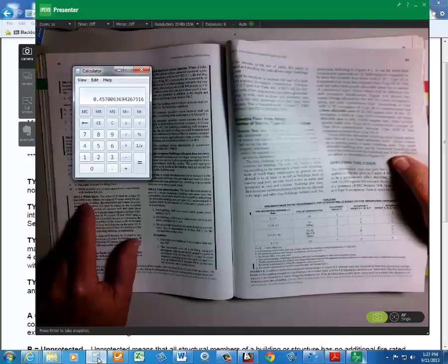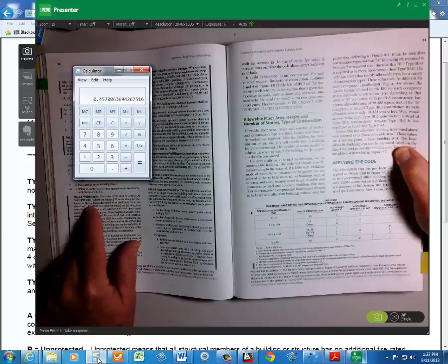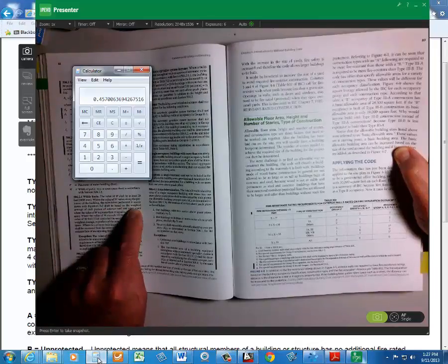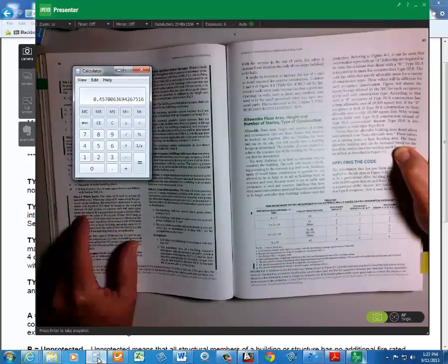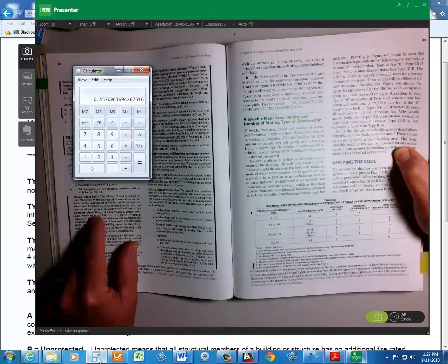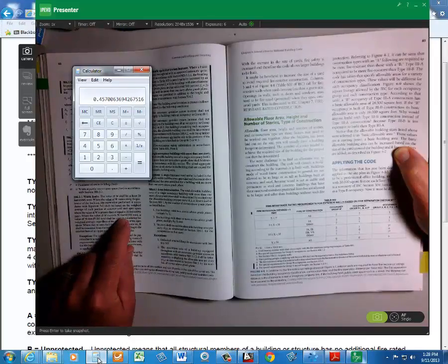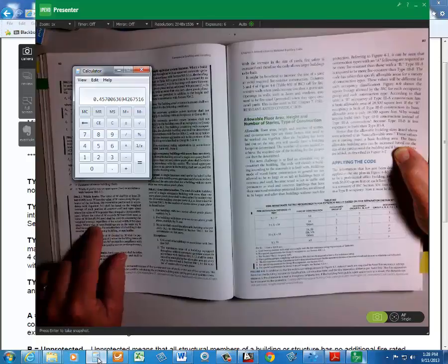Where the value of W varies along the perimeter of the building, calculation performed in accordance with equation 5-2 shall be based on the weighted average of each portion of the exterior wall and open space, where the value of W is greater than or equal to 20 feet. Where the value of W exceeds 30 feet, a value of 30 feet shall be used in calculating the weighted average.